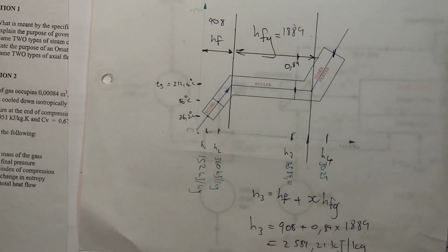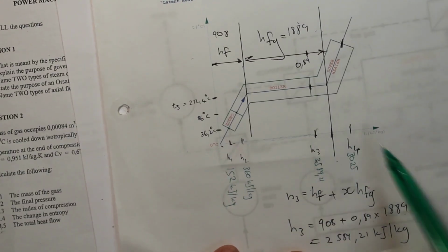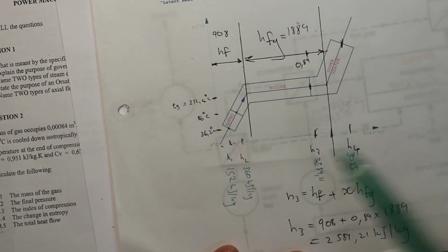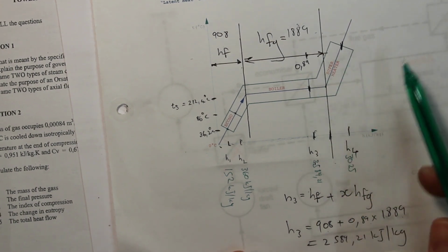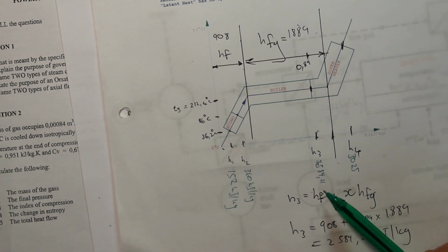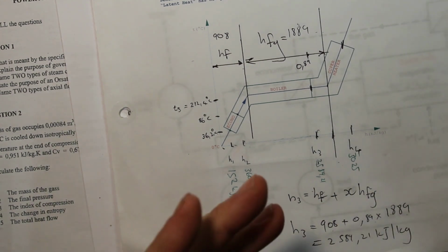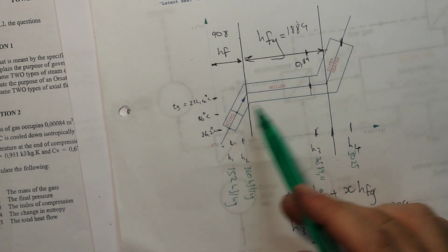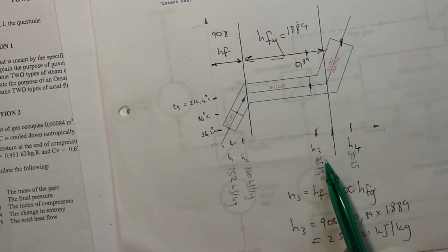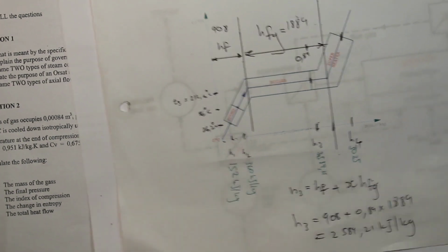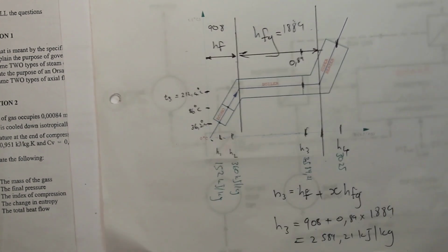All right. Now, how do we calculate the heat transfer in the superheater now? Okay, how much heat went into the superheater? So it's H4 minus H3. Okay, so you see how easy it becomes. H4 minus H3 is the superheater, and that's how we just subtract the two, and we get what the heat transfer in the superheater is. H3 minus H2, this section here is the boiler section. H2 minus H1 is the economizer section. All right, and that's that.